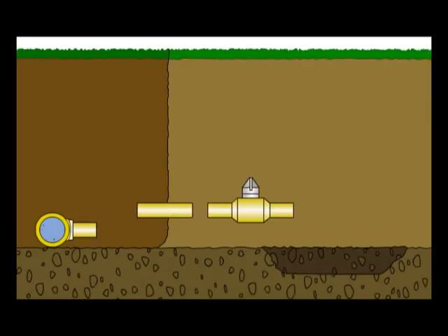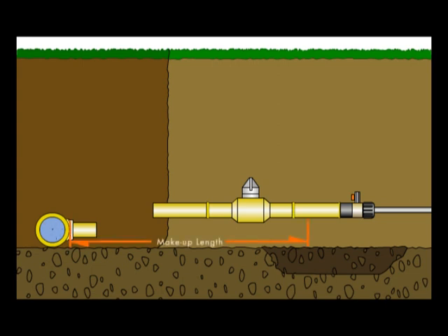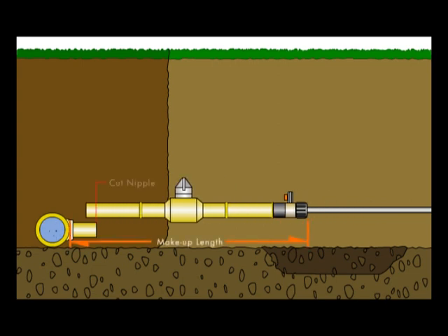A small piece of pipe called the nipple is fused to the valve and the hot tap tool is fused to the other end of the valve. The overall length of the tool is measured and the nipple is trimmed to the proper makeup length. The hot tap assembly is fused to the saddle fitting.